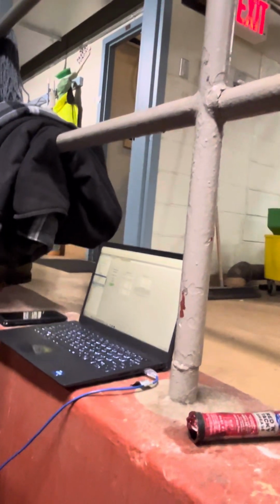So, system enable: we are going to enable if the outside air drops below 55 degrees. We automatically go enable. Pretty reasonable. 55 degrees is pretty standard; sometimes you'll see 60, sometimes, very rarely, we see 50, but 55 is pretty standard.